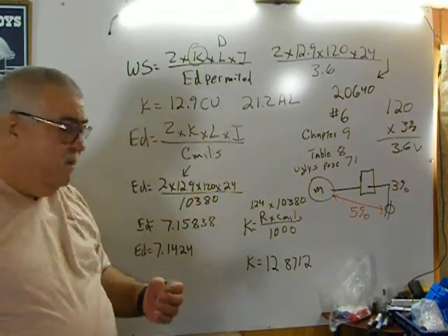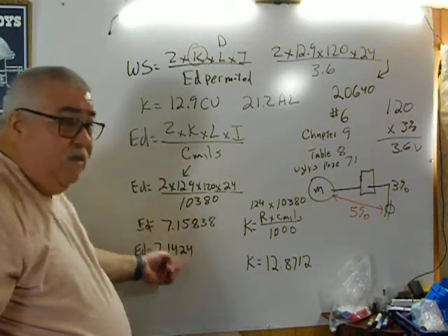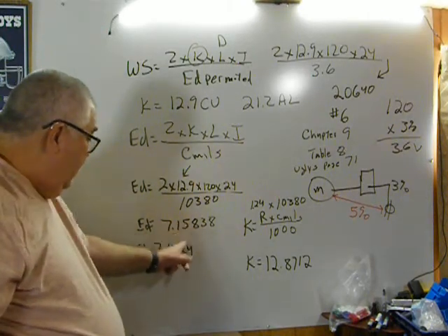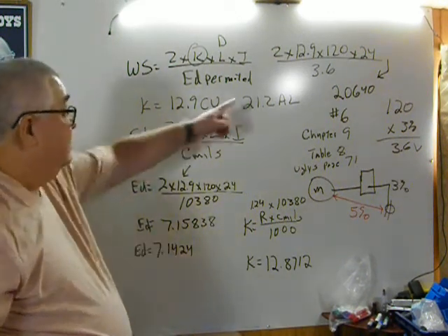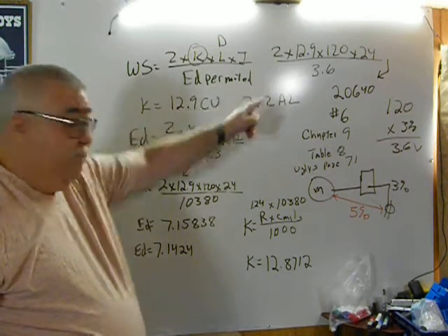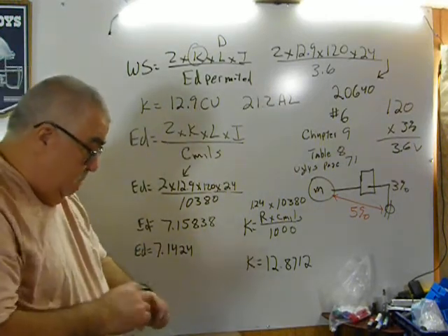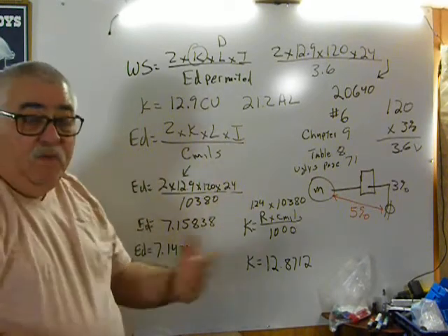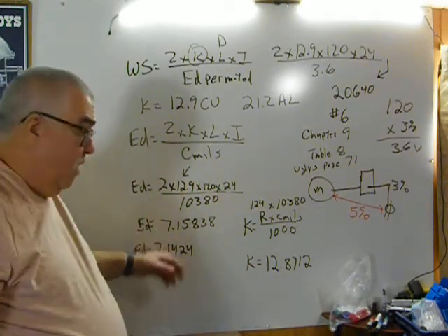If you're out in the field, this is all you need. Guess what? It's no different than this. That's hundredths of a percent here. That's nothing. Allowable voltage drop is 3.6, and I'm losing twice the amount. So I just make a correction on those wire sizes, knowing what I got.